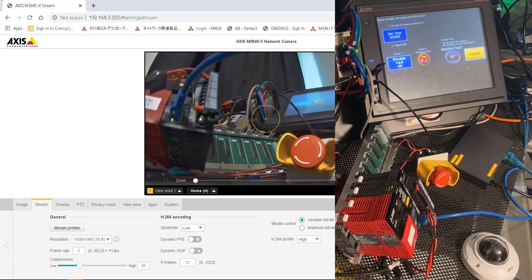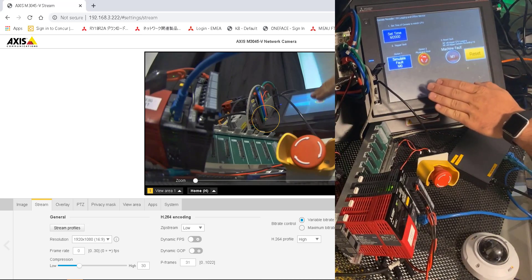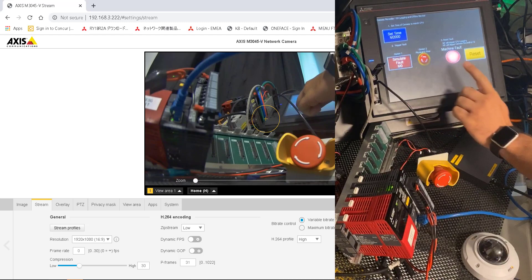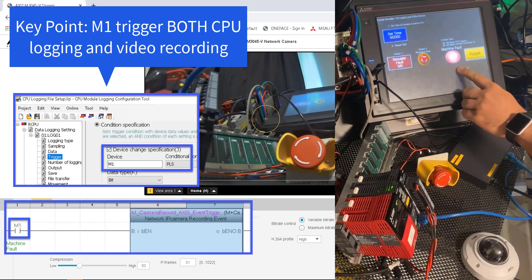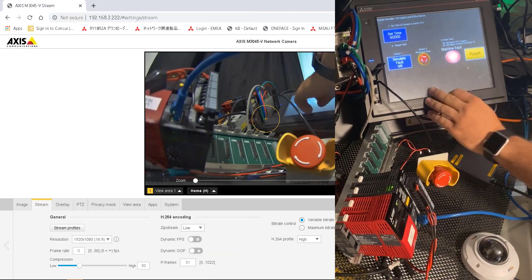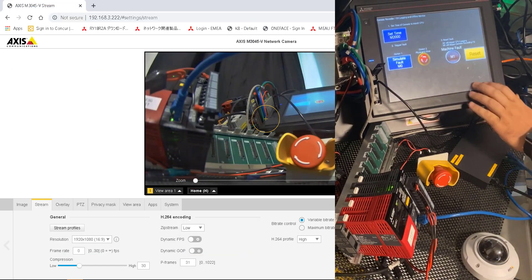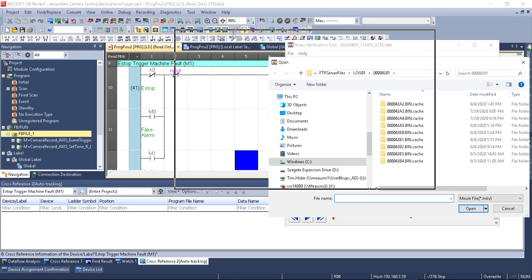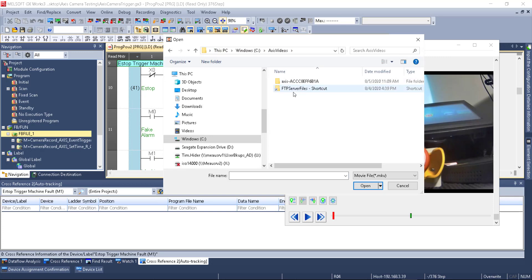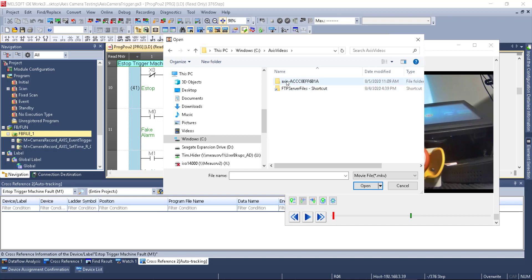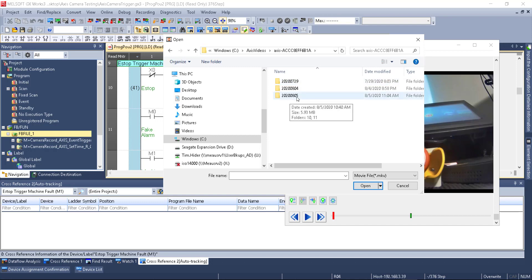Now that we've looked at the setup, let's trigger using the HMI. We simulate a fault by pressing the button — M1 is on. M1 is our CPU logging trigger and our camera file recording trigger, so that should have given us a file from the camera as well as a logging file from the PLC. We take the fault off, clear the fault, and go back to look at what happened. First we'll bring up the Video Verification Tool and point it at our video file — Axis Videos folder, August 5th 2020.